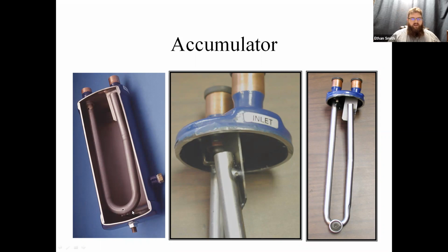In an accumulator that's got a plugged hole, what you'll notice is that oil level is much higher. And so your accumulator won't have a perceptible heat to it until you get above that oil level. Once you get above that oil level, that accumulator is able to retain the heat in the wall of the accumulator. And you'll notice that accumulator suddenly gets very warm along the path of that torch at the oil level.